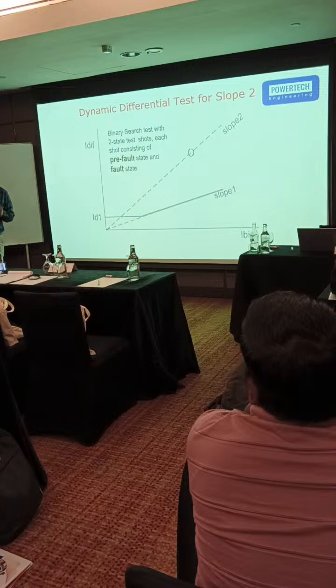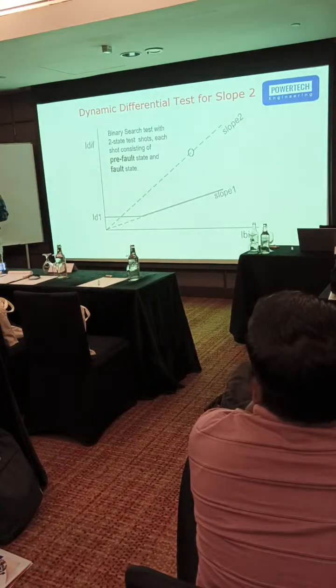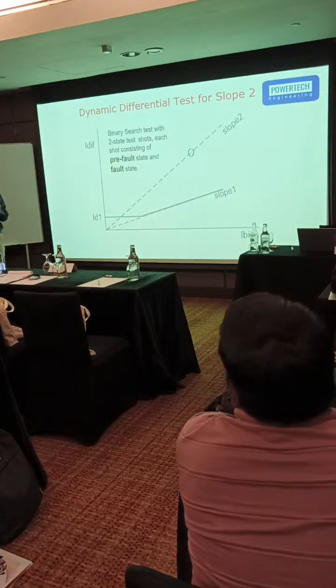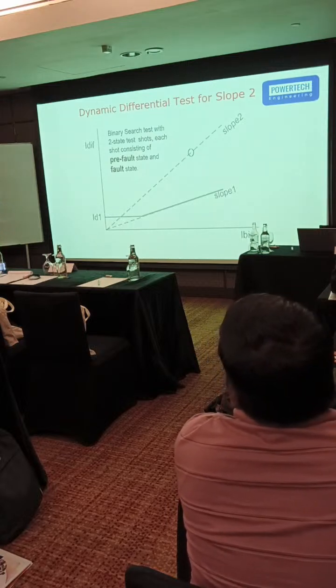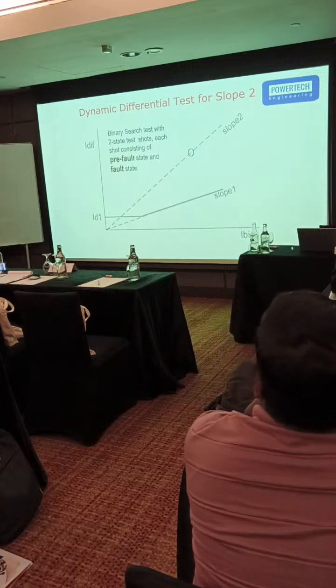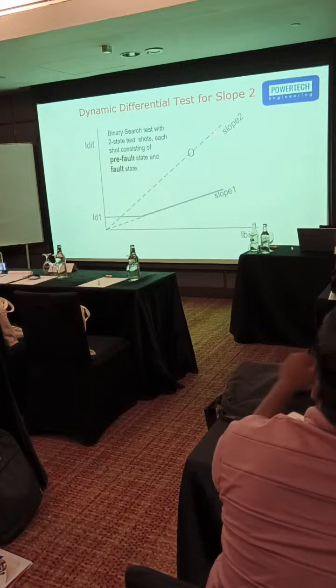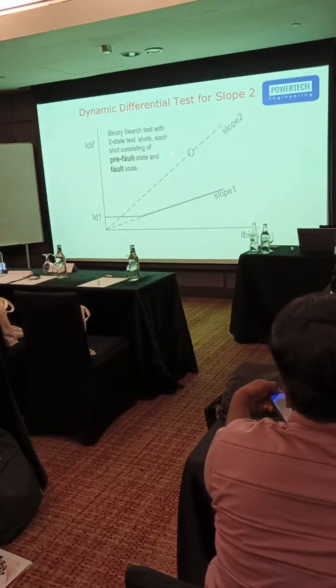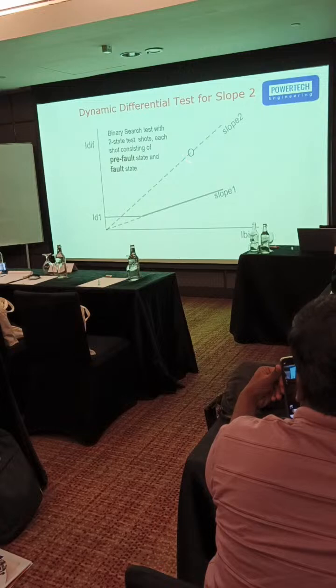So we are doing it through templates. Many have made this template as well, but Doble does not have this template. So we use it for slope 2 testing. We have to use the state simulation method in that case, because if there is no delay, then we cannot achieve this slope.